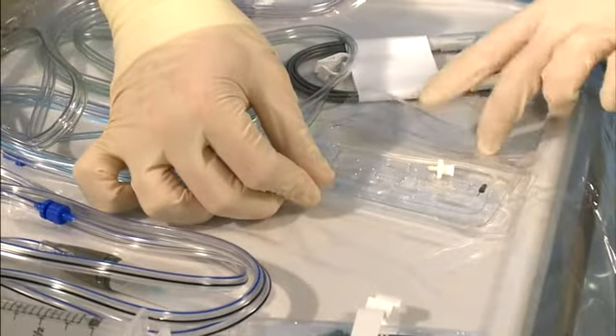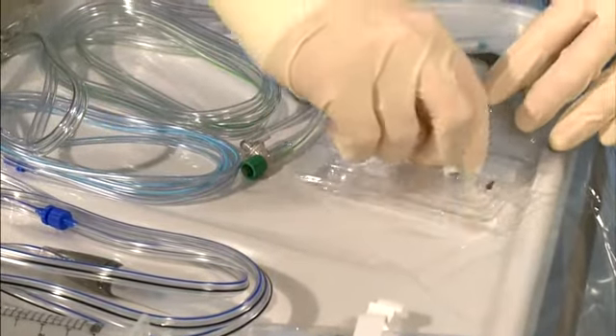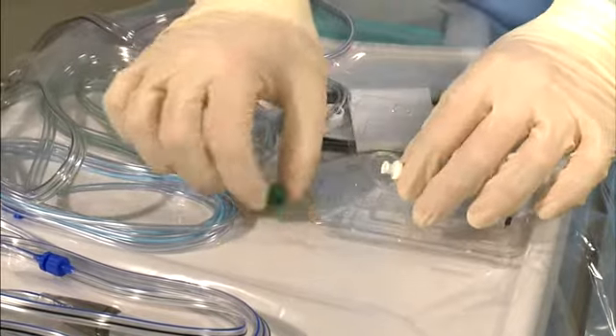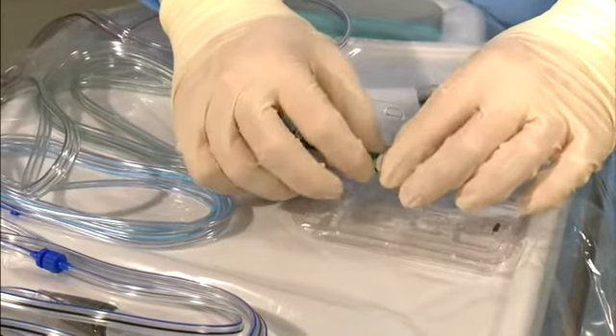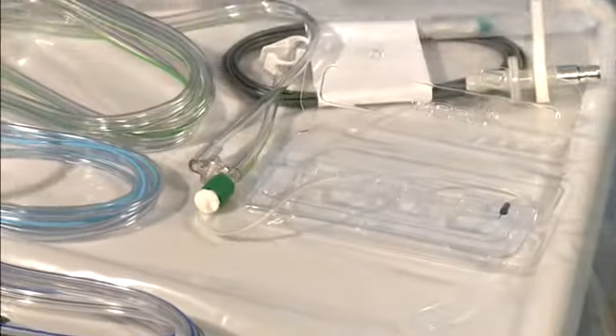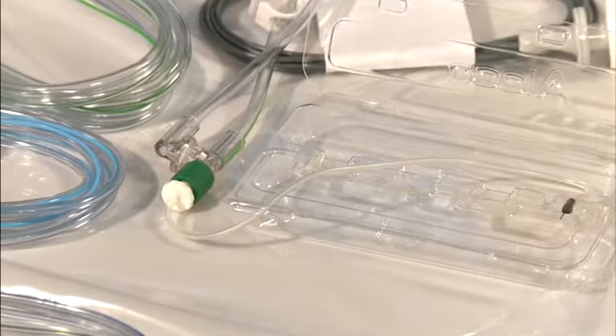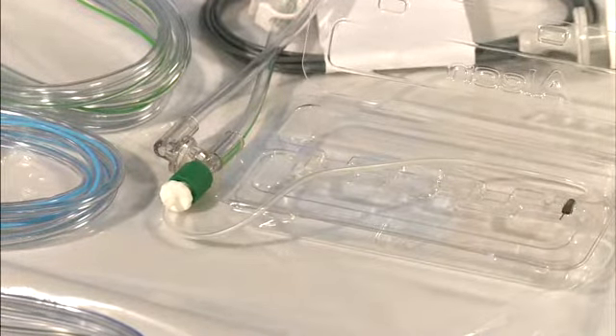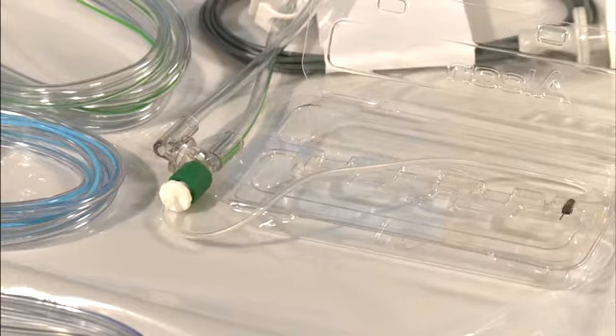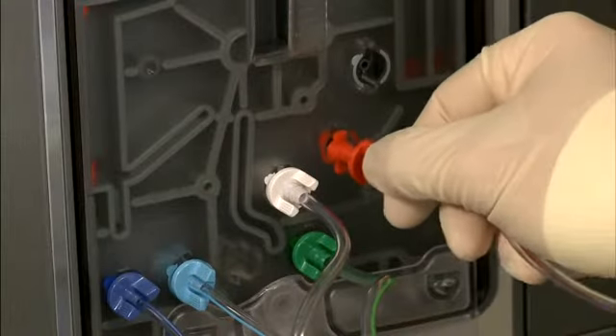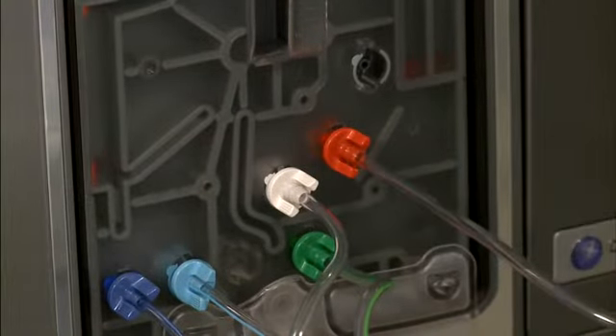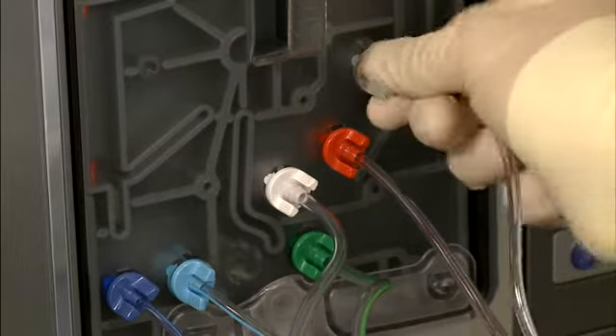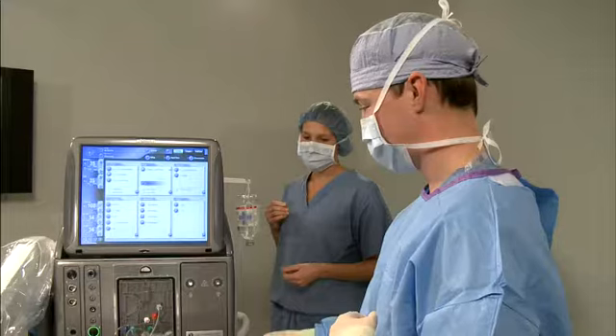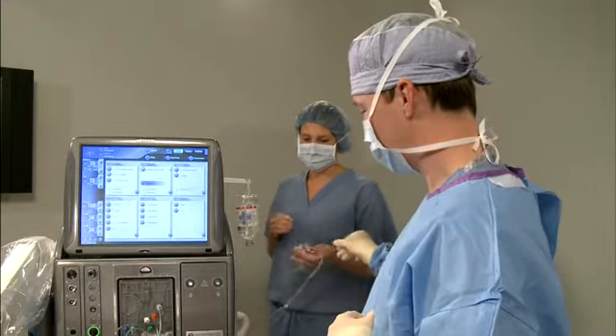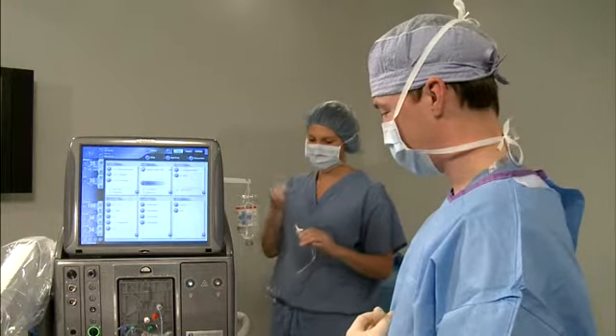Next, open one flap of the infusion cannula tray to gain access to the luer fitting. While keeping the cannula in the tray, connect the fitting to the green infusion line. The tray must be set on a flat surface in preparation for priming and calibration. Connect both the red and gray connectors of the administration tubing set to the cassette. Pass the drip chamber to the circulator directly or set the drip chamber on the bottle hook.